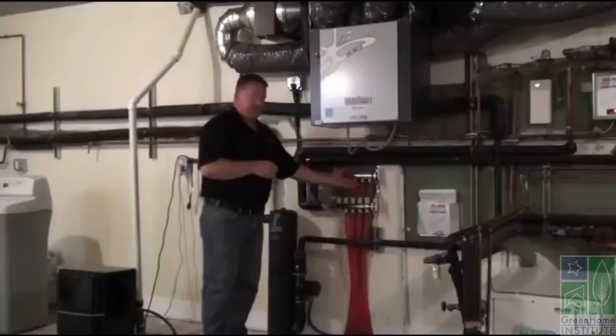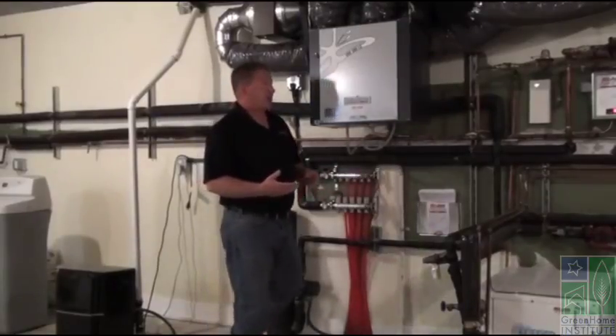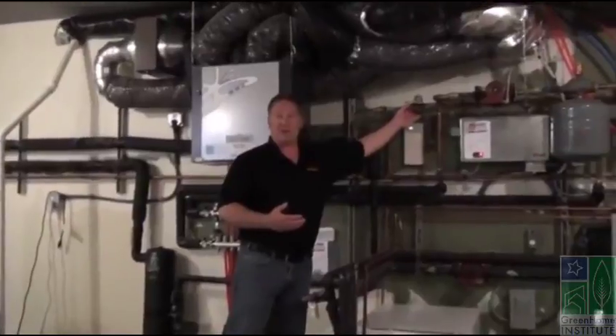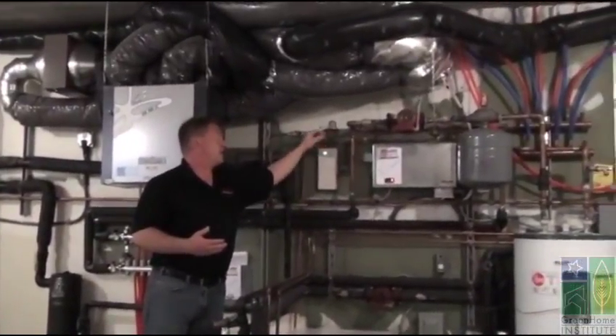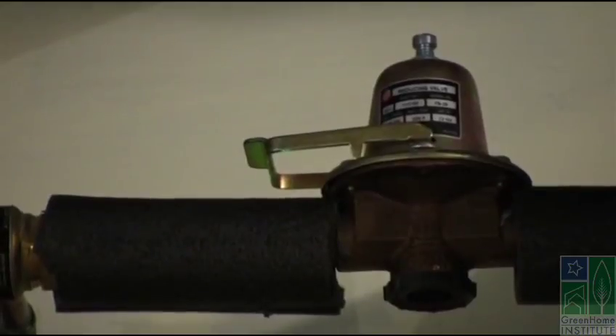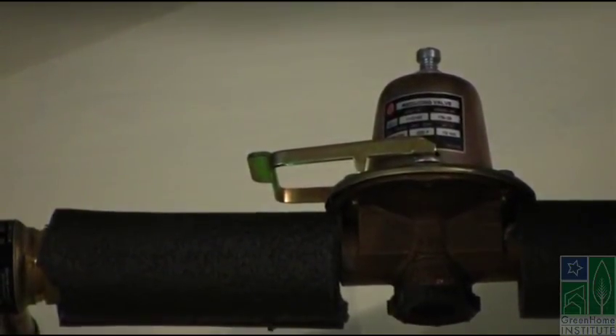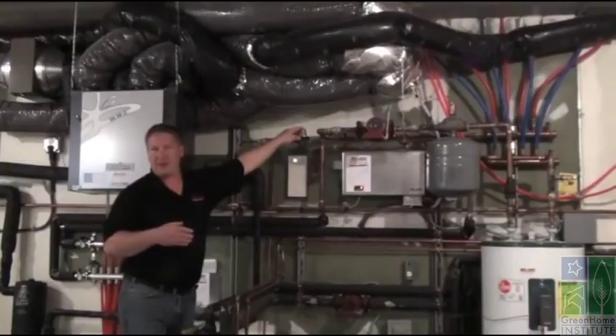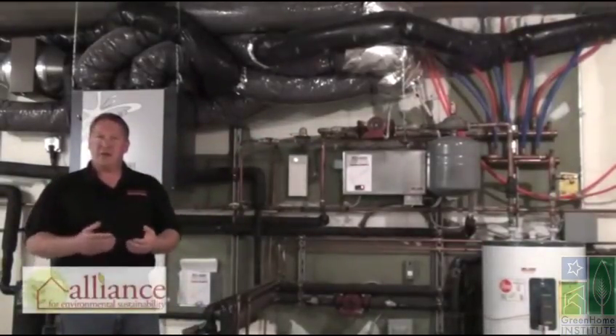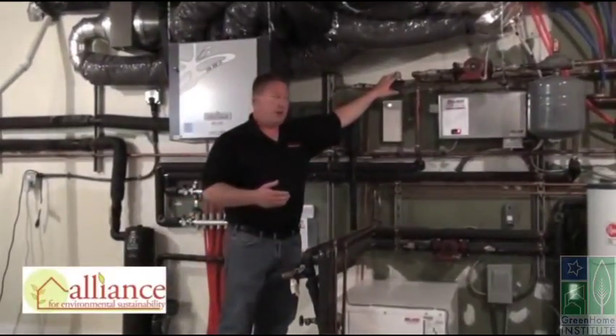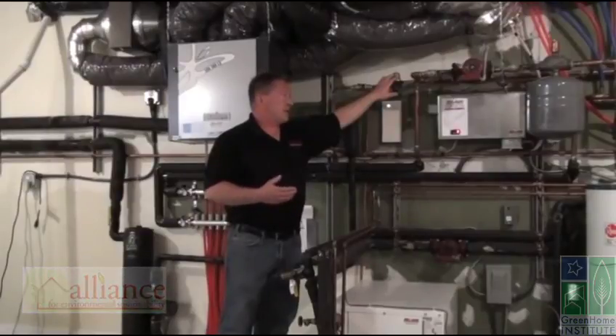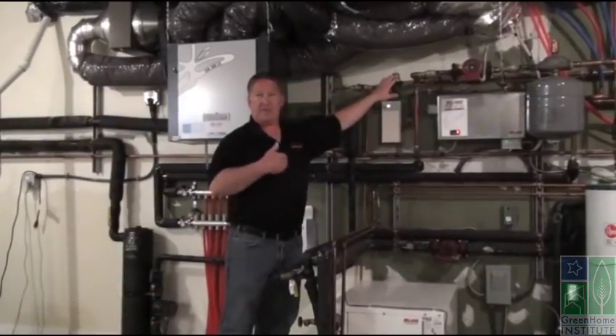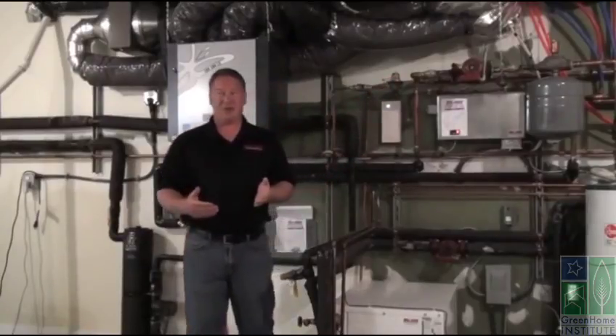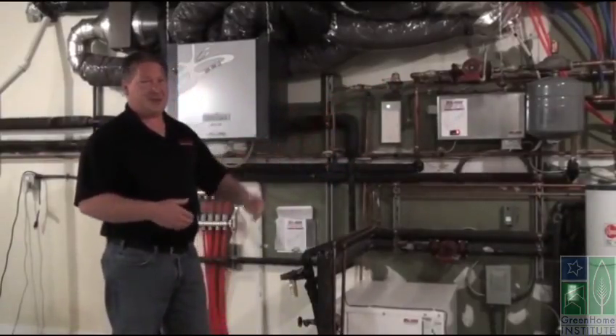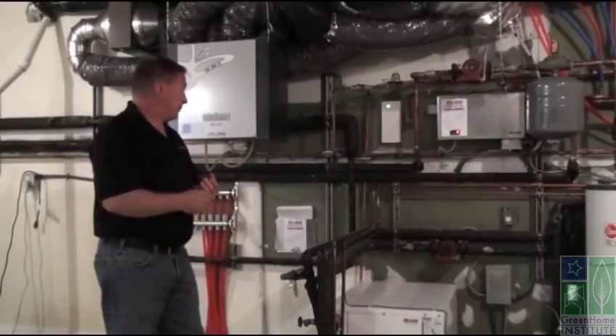If one of these springs a leak, then you're obviously going to have water. There's an automatic system here that refills the system. So if water leaks out, this is called a pressure reducing valve. We don't put city water pressure into those pipes. It's actually only at 12 psi, and your city water pressure or well system operates somewhere around 50 or 55 psi. So this reduces that pressure down to 12, cold fill pressure. Again, if there's a leak, this will turn on and fill the system back up with water, which can be an issue if you're not around and there's a leak somewhere. It's just going to continually start pumping water into that.